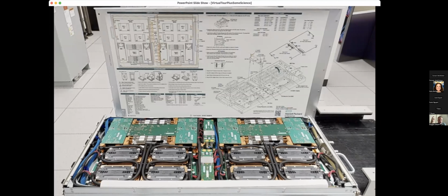The water gets heated to about 120 degrees Fahrenheit by the time it's washed over these hot components. Thermodynamically, all that really matters is the delta between the hot and cold side, so we get about a 30 degree Fahrenheit difference. That tells us how much heat energy we're pulling out of the cabinets at any given time. Since we don't have to chill that water down further to make it really cold, that's a huge power savings for us.